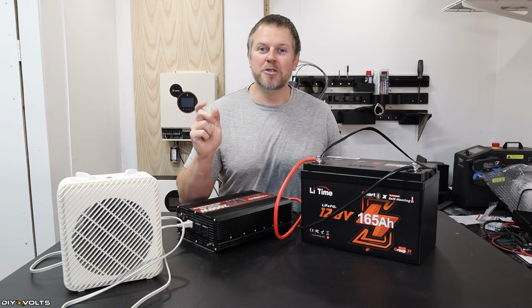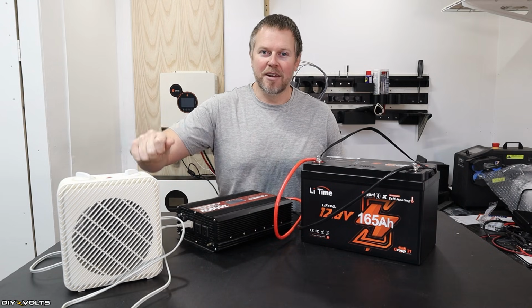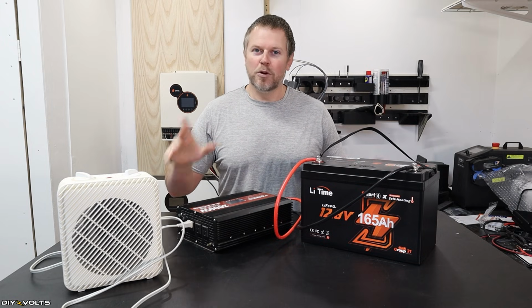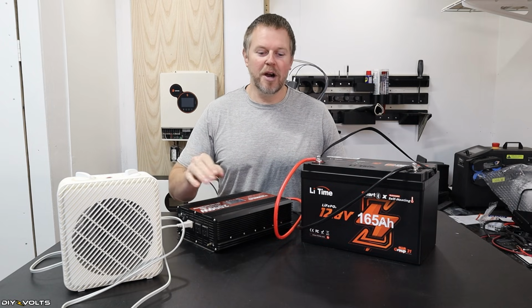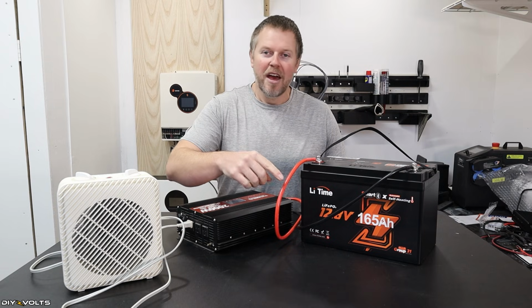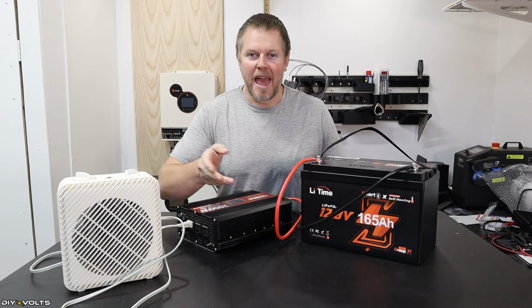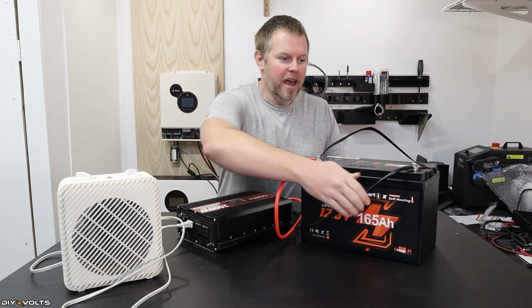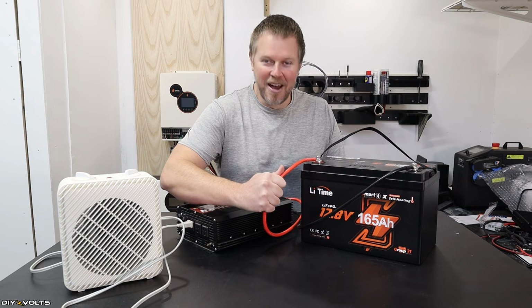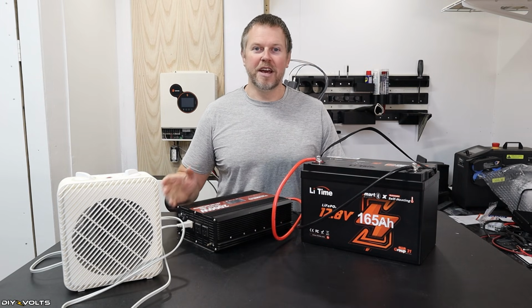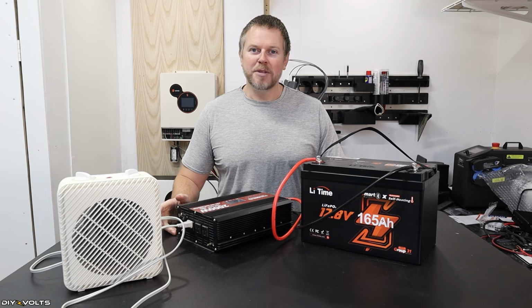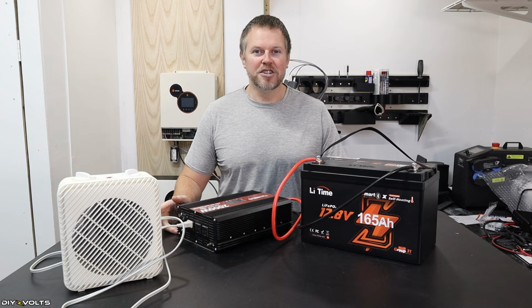Now, immediately after showing you the app, I clicked this down to setting number 2, because 1,400 watts seemed like too much for my 6-gauge wire at 120-something amps. So I dropped it down, and the wires are no longer getting hot. We should be able to run this for the next 2 hours. I'll keep you updated and come back when the discharge test is done.